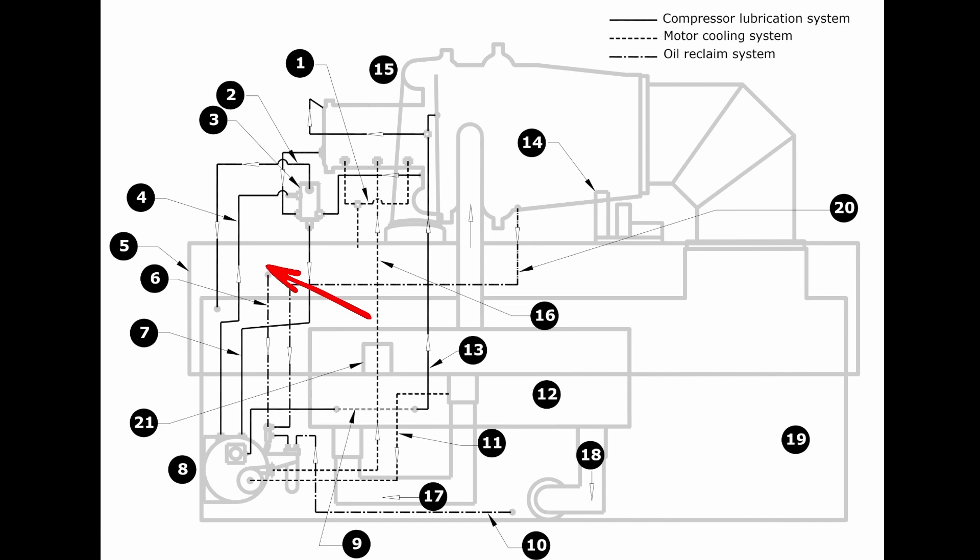Then we will have a high pressure condenser gas line that flows from the condenser into this block. That high pressure condenser gas flows through a nozzle assembly which creates a venturi effect, which is basically just a siphoning effect.